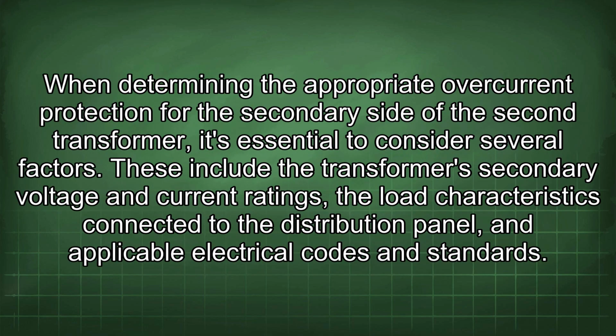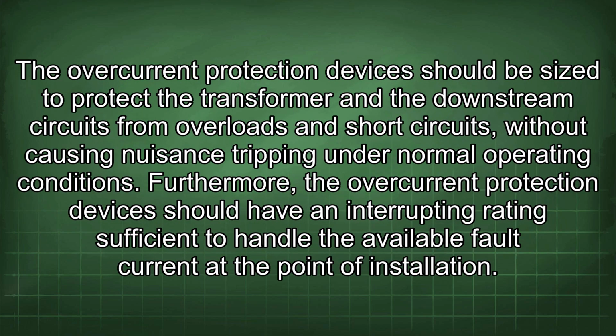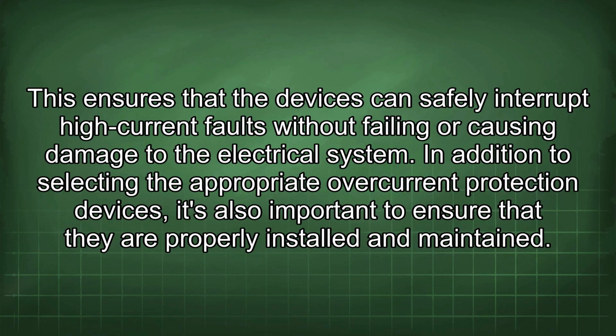When determining the appropriate overcurrent protection for the secondary side of the second transformer, it's essential to consider several factors. These include the transformer's secondary voltage and current ratings, the load characteristics connected to the distribution panel, and applicable electrical codes and standards. The overcurrent protection devices should be sized to protect the transformer and the downstream circuits from overloads and short circuits, without causing nuisance tripping under normal operating conditions. Furthermore, the overcurrent protection devices should have an interrupting rating sufficient to handle the available fault current at the point of installation.